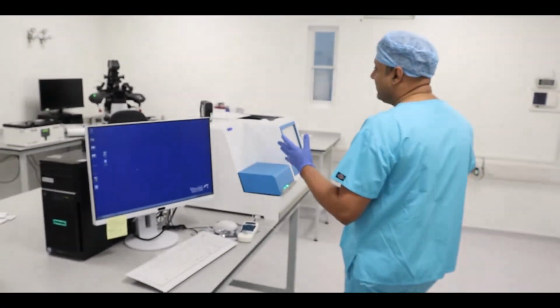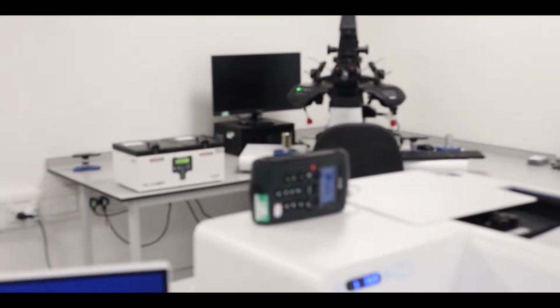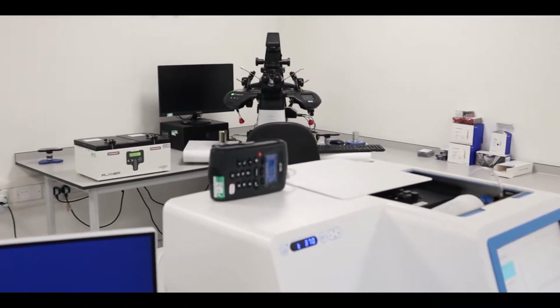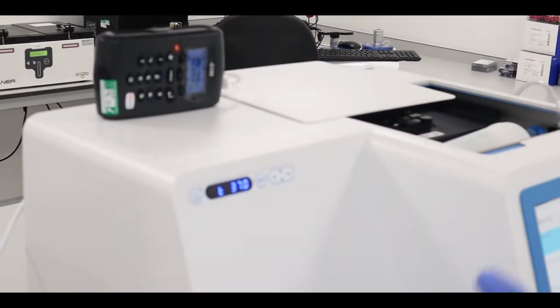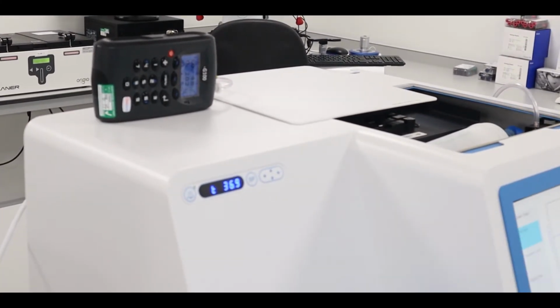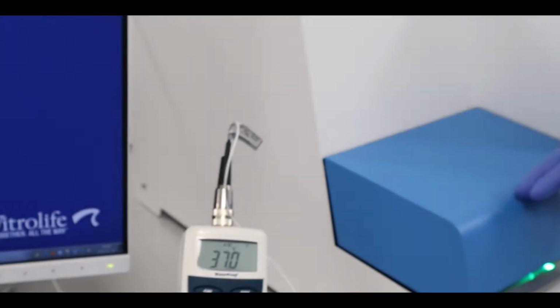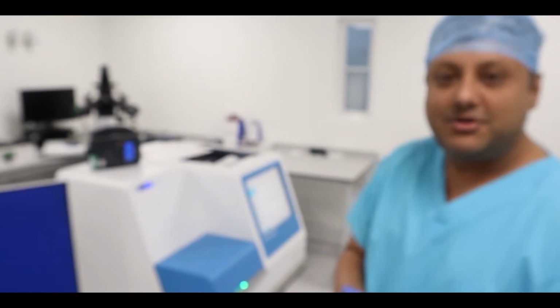So here we are with the EmbryoScope, and we're doing some temperature and carbon dioxide checks. The typical temperature we would like on incubators is between 36.9 degrees and 37.0 degrees. Now the body temperature is around 36.9 or 37.0, and here we are. You can see that we're measuring independently the temperature in the incubator, which is at 37.0, and we're just going to be running the carbon dioxide to check what the carbon dioxide is reading, but at the moment it's reading 4.9. We ideally want it to be anywhere around 5 to 6%.